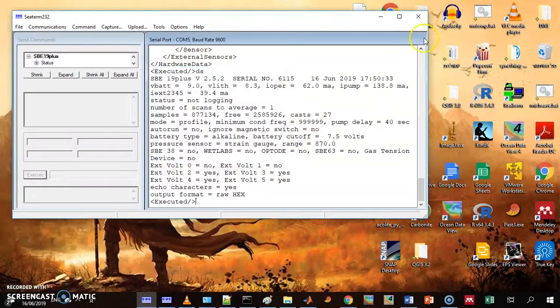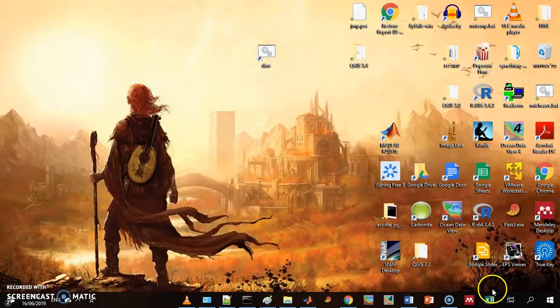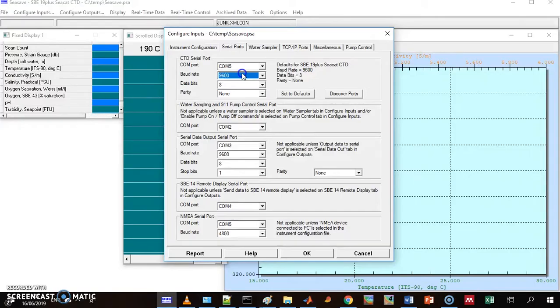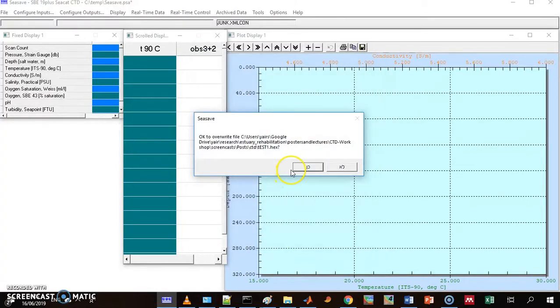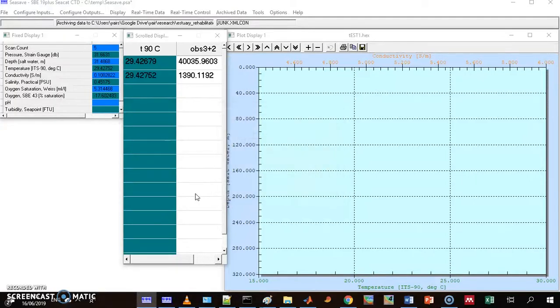So now I'll exit SeaTerm, again go to SeaSave, 9,600. Okay, I switch on the device and start, and communication is formed. So my baud rate was wrong, and we're done with this screencast.